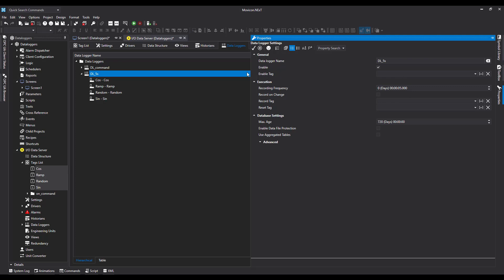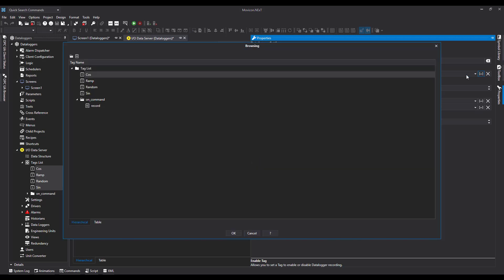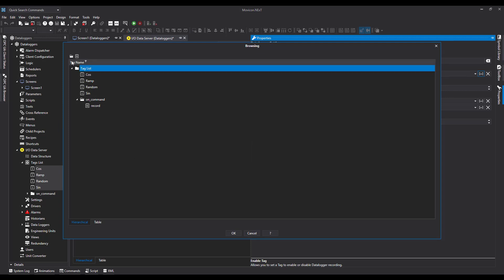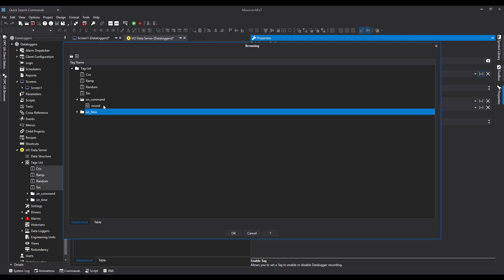We have this Enable Tag here. I'm going to hit the three dots and it's going to bring me to my tag list. I haven't got a tag for it at the moment, so I'm going to create a folder to keep it nice and tidy. Call this one OnTime. Then I'm going to create a tag in there which is a boolean, and I'm going to call it Enable.DL just to make it nice and simple.